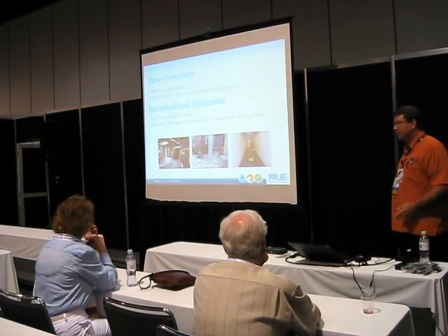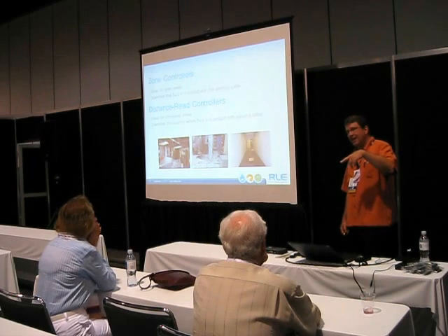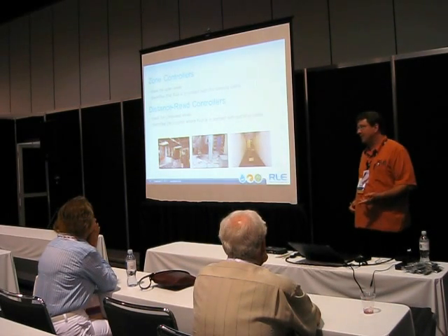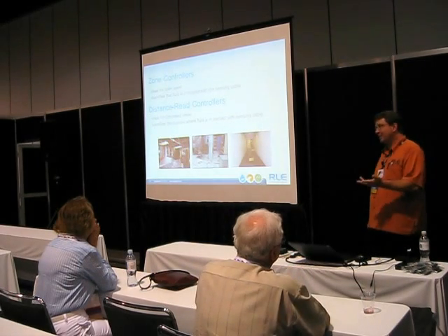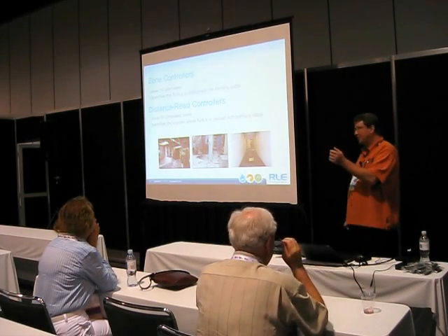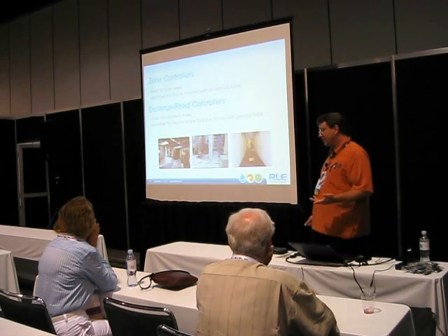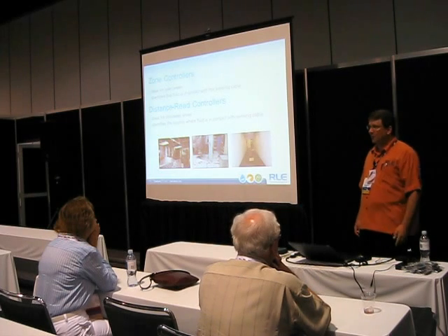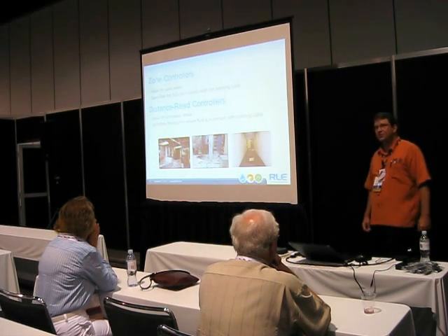But what that'll actually do is we can run well over 5,000 feet of cable. And if water comes in contact with it, it'll actually give you a display. Some controllers will call your cell phone, give you direct notification, let you know exactly where that issue is. Maybe even a visual indicator on a map showing you where the problem is. So you walk into an area, for example, like a data center, raised floor environment, you can literally lift one floor tile, take care of the problem. There's no hunting and searching, trying to figure out where those issues are.